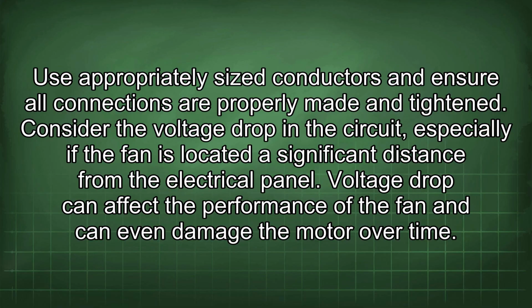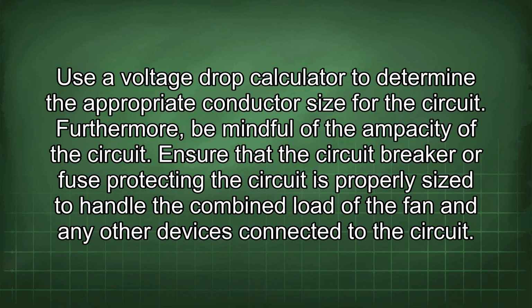Consider the voltage drop in this circuit, especially if the fan is located a significant distance from the electrical panel. Voltage drop can affect the performance of the fan and can even damage the motor over time. Use a voltage drop calculator to determine the appropriate conductor size for the circuit.